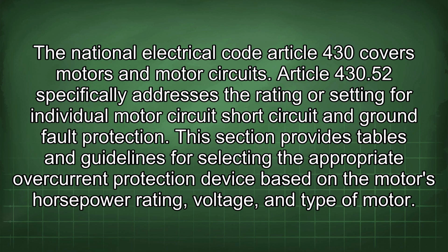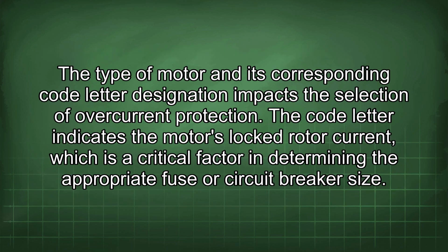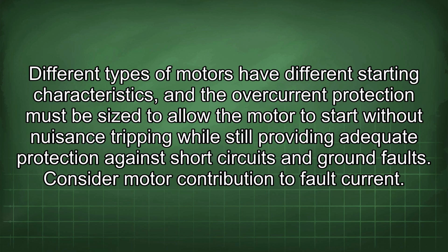and type of motor. The type of motor and its corresponding code letter designation impacts the selection of overcurrent protection. The code letter indicates the motor's locked rotor current, which is a critical factor in determining the appropriate fuse or circuit breaker size. Different types of motors have different starting characteristics, and the overcurrent protection must be sized to allow the motor to start without nuisance tripping while still providing adequate protection against short circuits and ground faults.